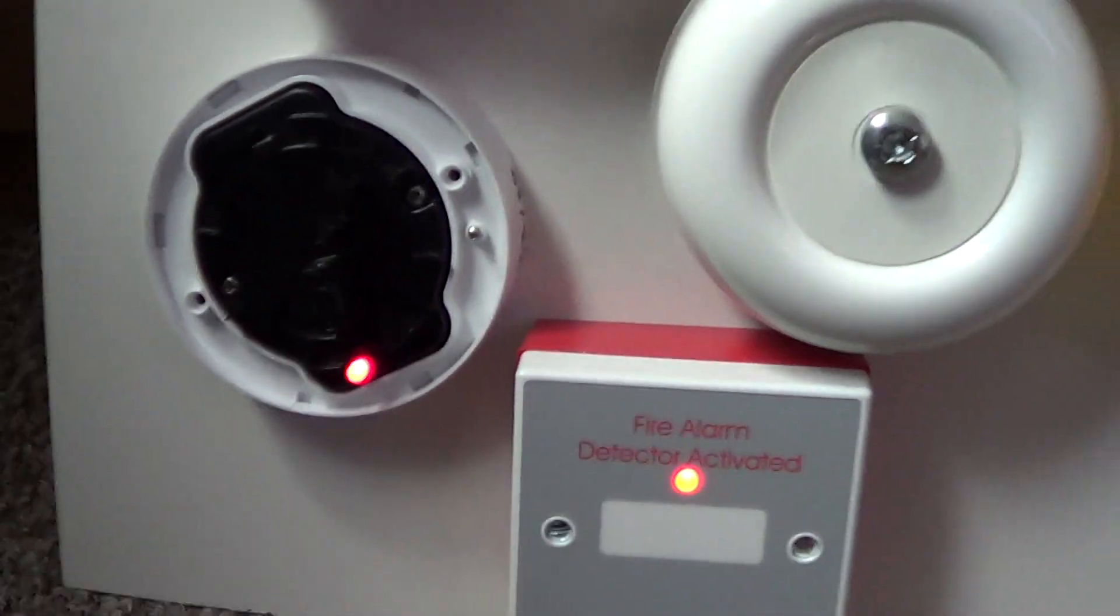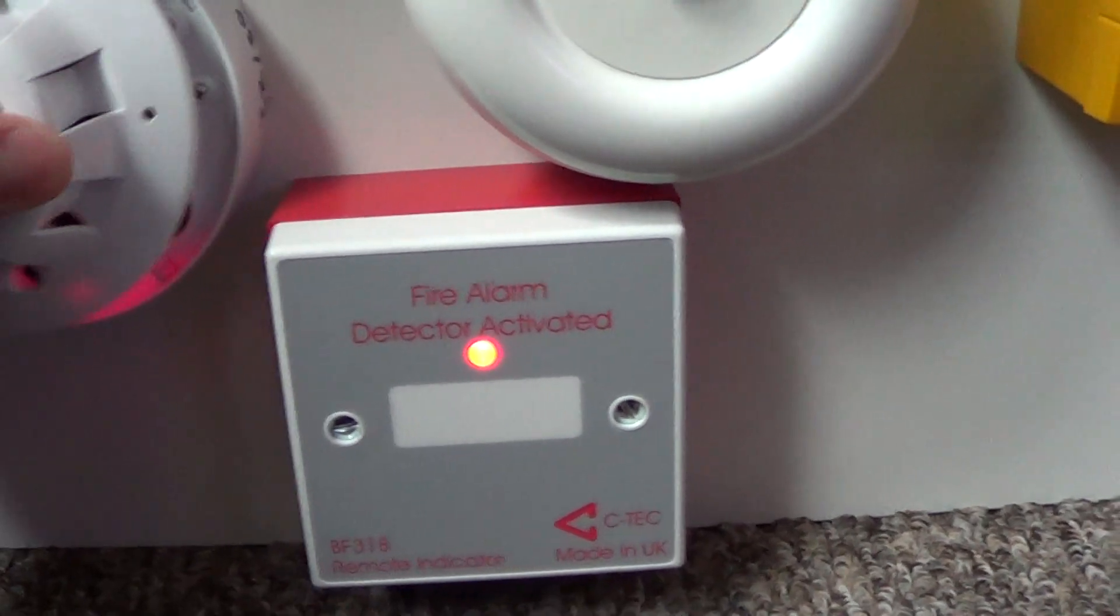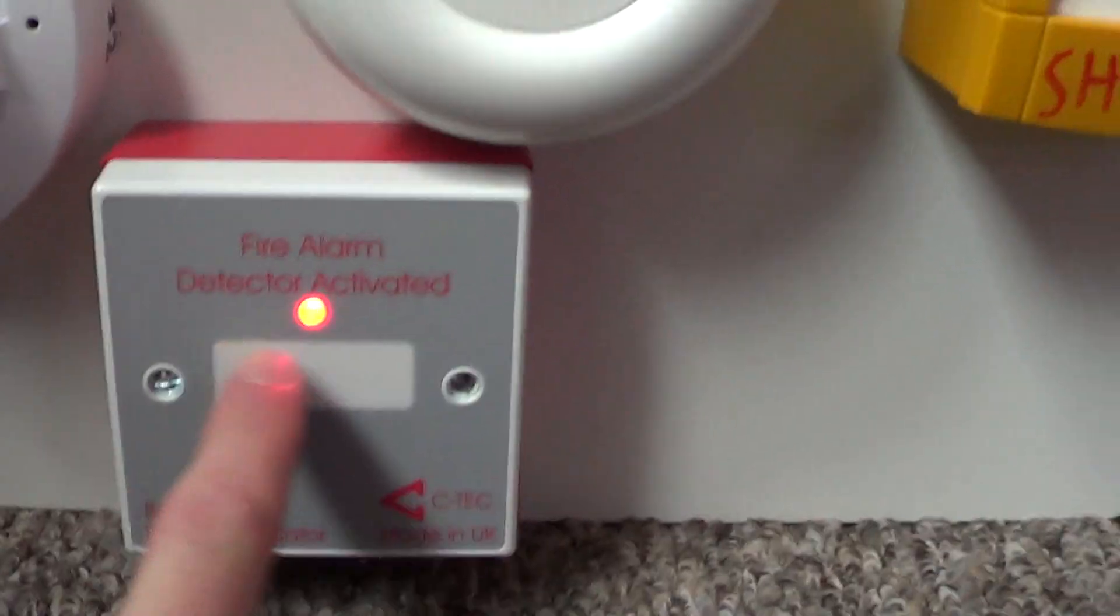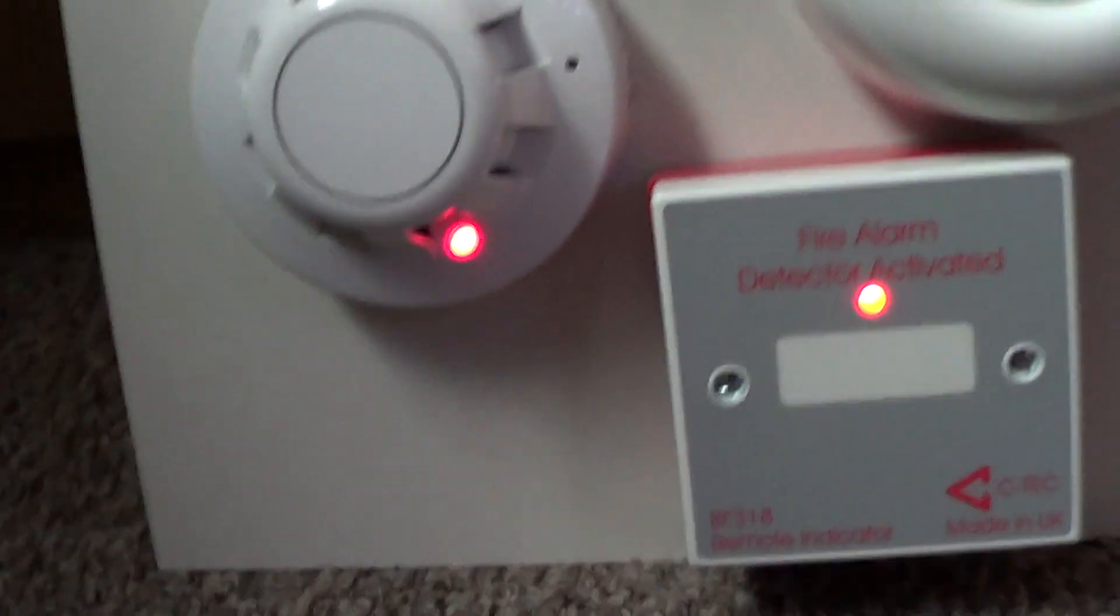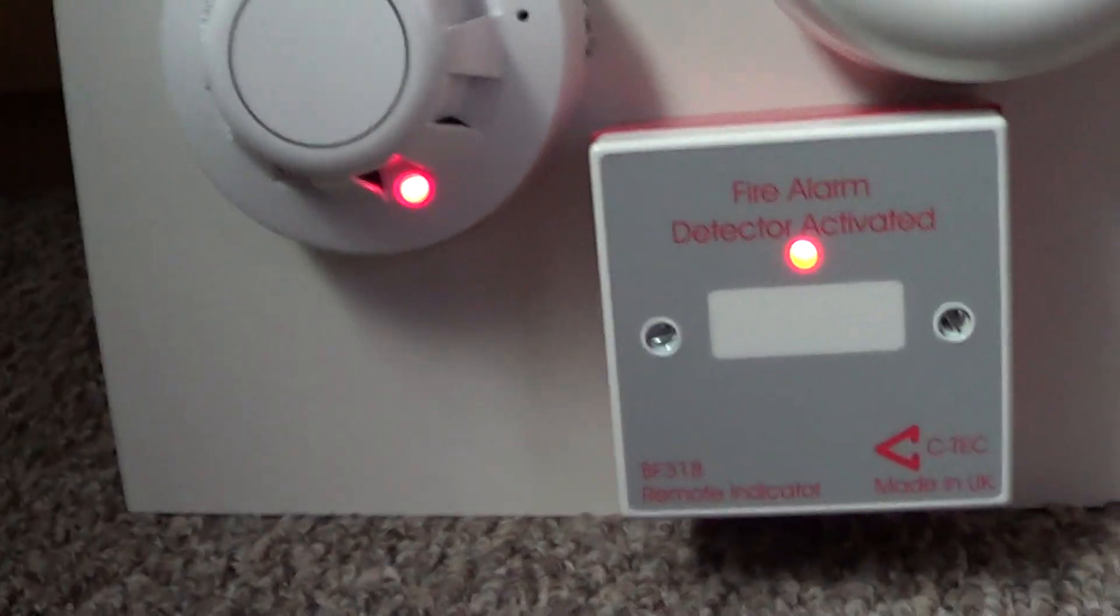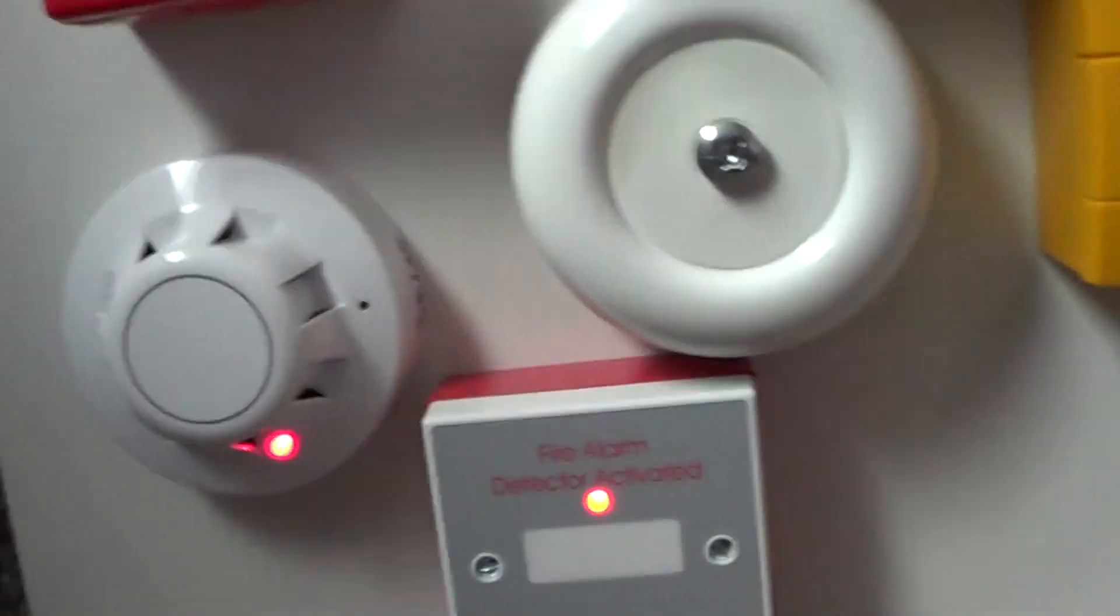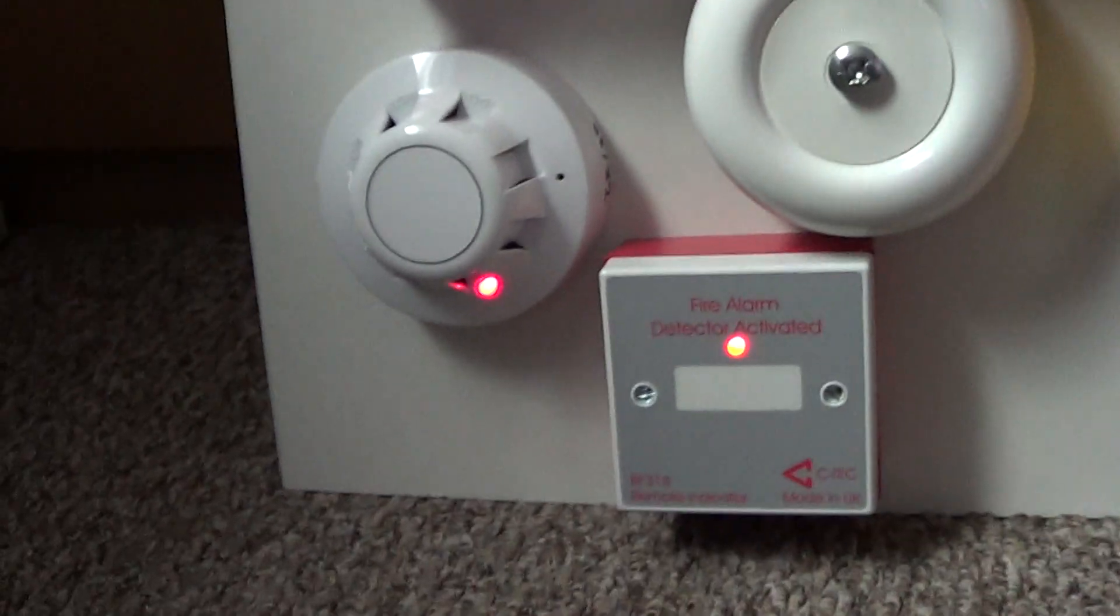So the remote output indicator will show if this smoke detector is activated, if it's in a hidden location for example. If it was in a cupboard that's locked up that only certain people are allowed to get into, it would allow anyone to see that the smoke detector in there or the device has been activated.